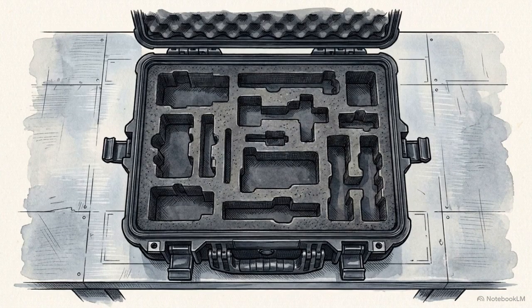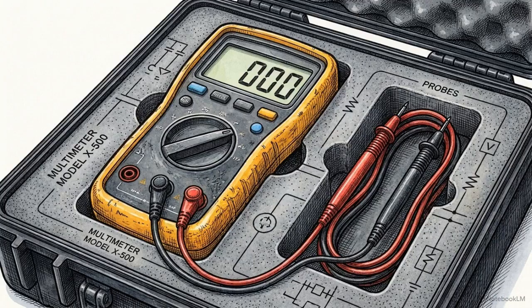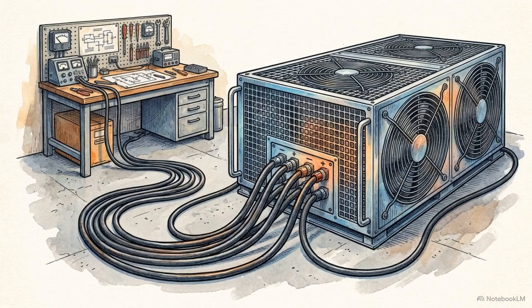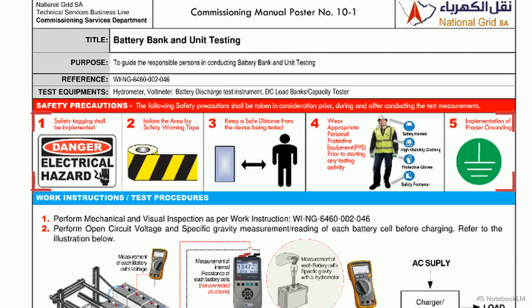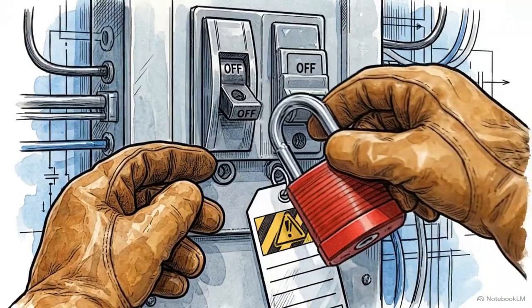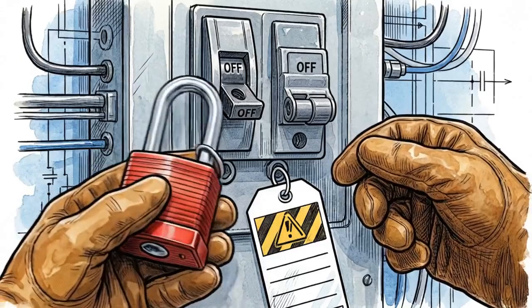To execute these physical tests, we rely on a specific set of primary diagnostic tools: a hydrometer to measure fluid density, a calibrated digital voltmeter, an internal resistance tester, and a DC load bank to simulate electrical demand. This commissioning document dictates the strict 5-point physical safety protocol that must be enacted before a technician even approaches the live battery rack. First, technicians implement lockout-tagout, or LOTO, protocols on the main circuit breakers to completely isolate the system from the rest of the substation.